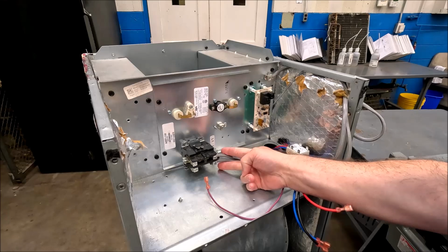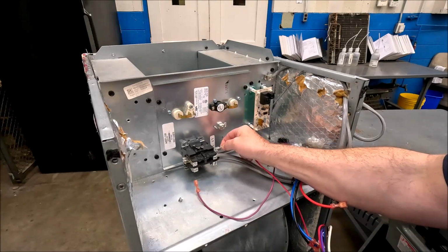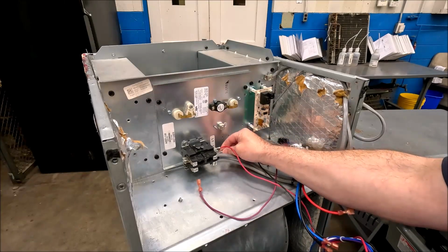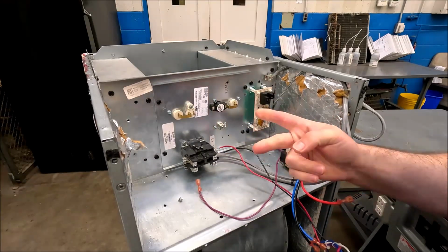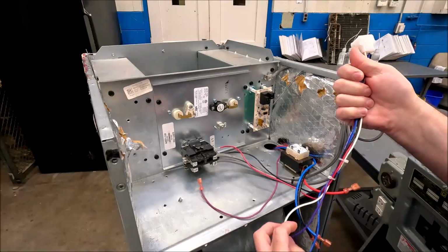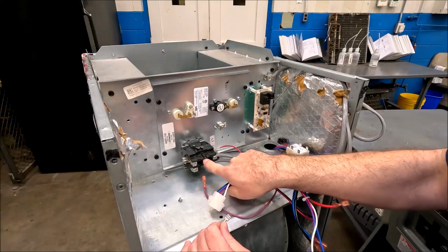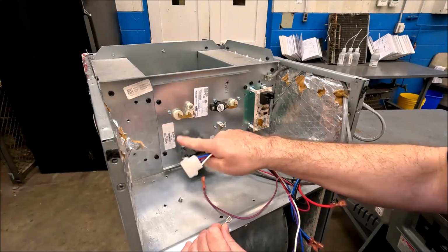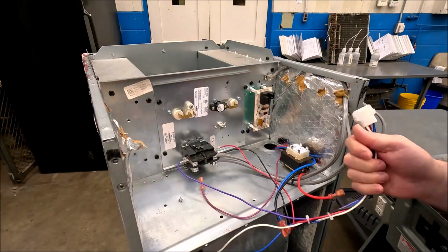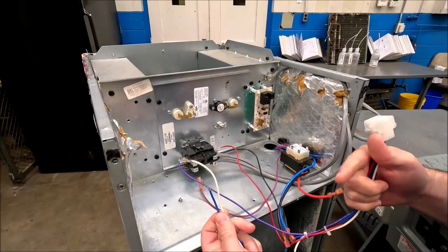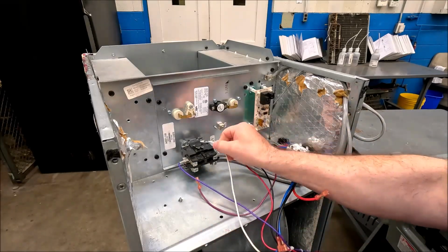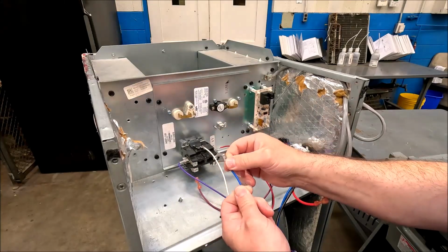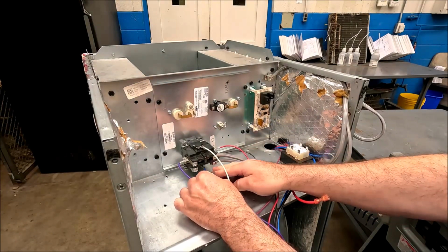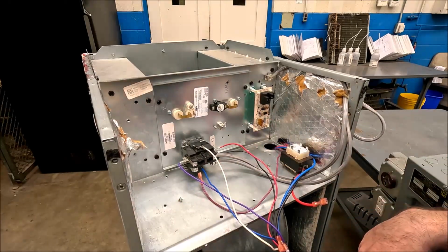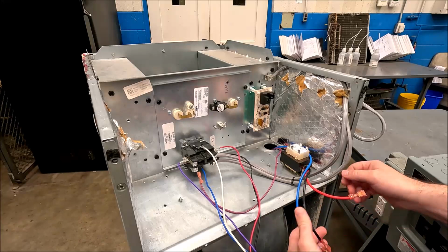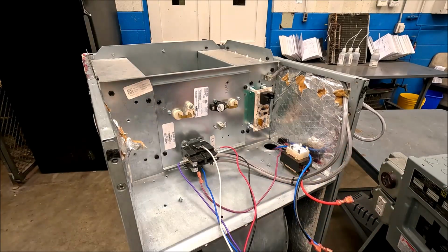So I'm just going to connect this back to my L1 and L2. So that's going to be red and black, and I'm doing it my way because I know what I've changed in my head. Okay, this purple wire here, that's after the switch. So power, control, and then the load side with the heater is where that purple wire goes. All right, and the last two wires in this plug are going to be your 24 volt. I'm going to put the 24 hot on top, and since common is worth nothing, I'll put it underneath on the contactor coil, and that way if anybody ever did anything with it, it would not short or pop a fuse or anything. So that's your female plug.